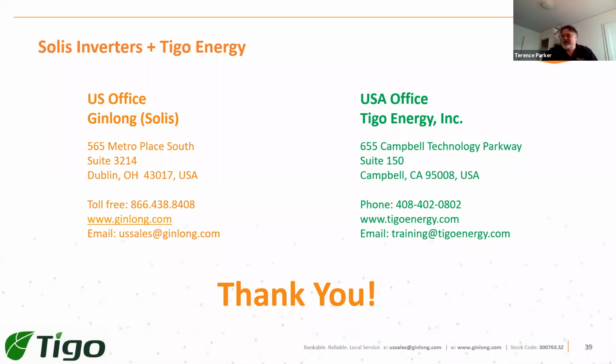We have talked about a super simple rapid shutdown solution here, but there are other things that Tigo can supply here. And with our 4 MPPTs on each one of these commercial inverters, you may be able to load up most of your system on 3 of them and then reserve that 4th one for maybe a troublesome string that you want to apply some selective optimization on. Right. The more MPPTs you have, the more likely it is you'll be able to just have one string per MPPT and selectively deploy all you like.